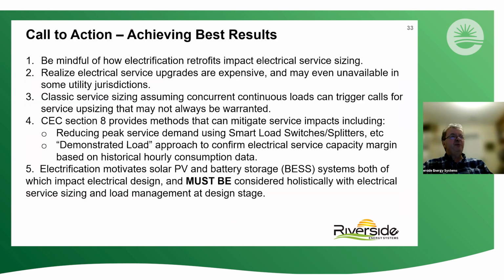So how do we do this well? Let's be mindful that electrification does impact service sizing, and that upgrades are expensive and maybe even unavailable in some utility jurisdictions. Classic service sizing assumptions could trigger calls for upsizing that might not be warranted if we dig a little deeper. Section 8 of the code also provides mitigation methods like load switches, smart load switches, splitters, and in particular this demonstrated load strategy, which I think will have real impact.